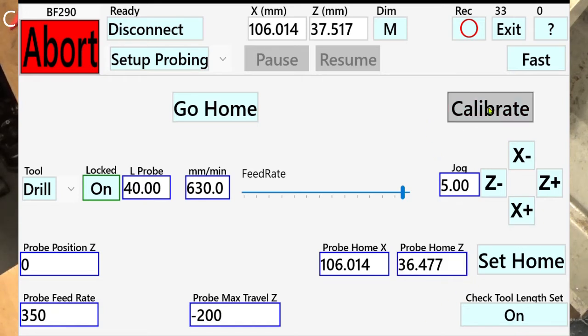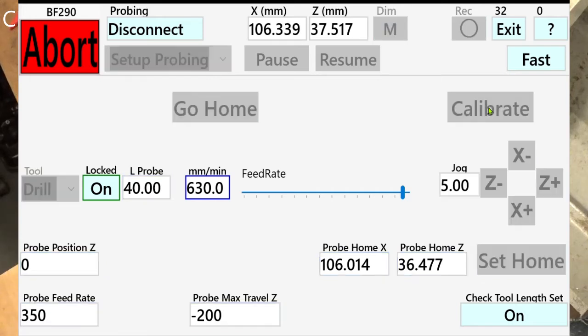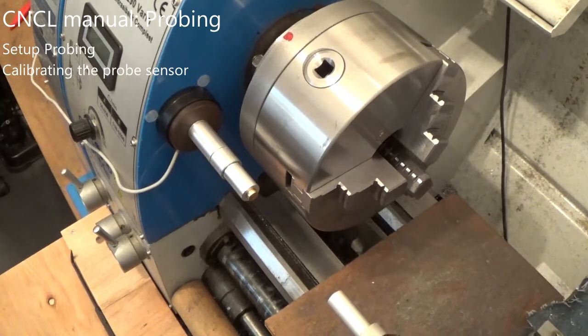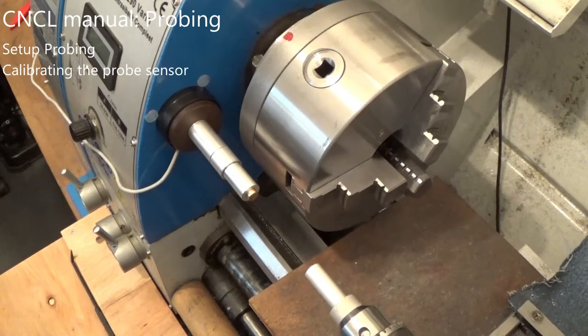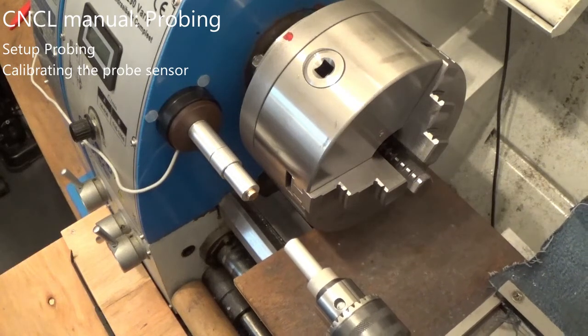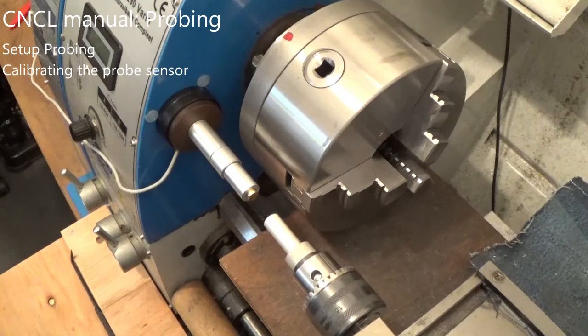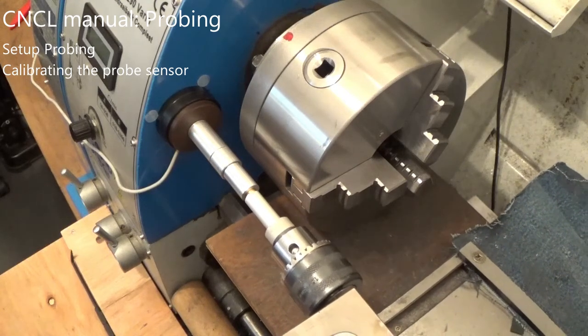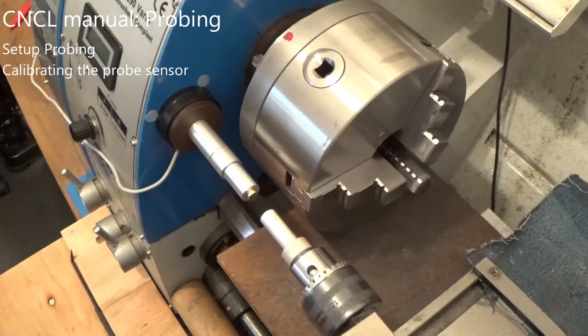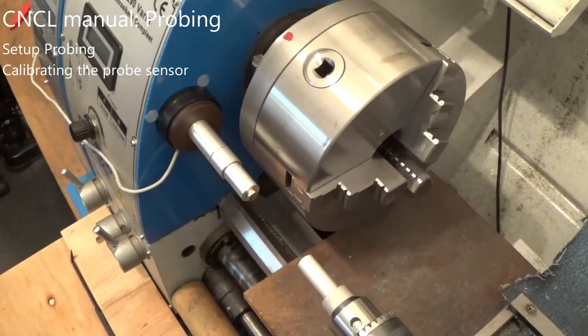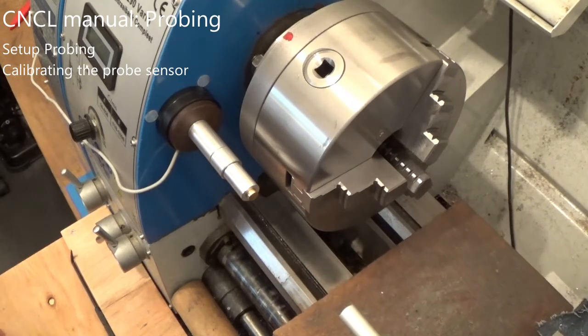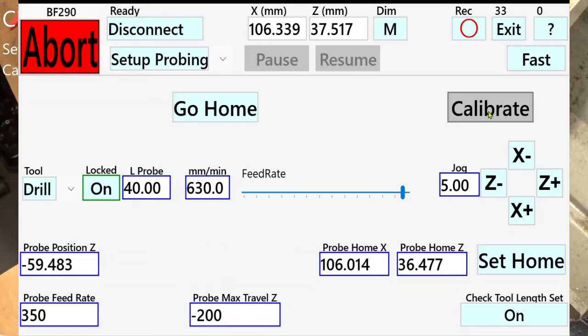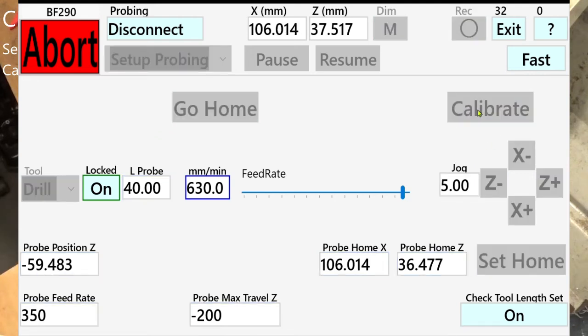Press the Calibrate button to calibrate the probe position. I found a probe position of 59.48 millimeters in the Z minus direction. When I hit calibrate again, I should find the same value within a hundredth of a millimeter.